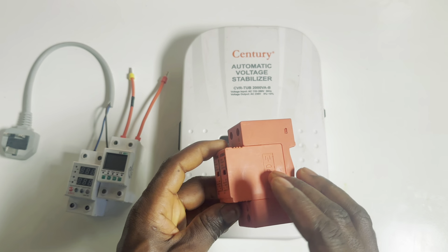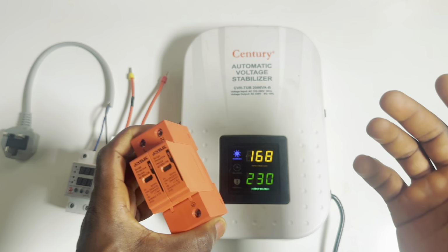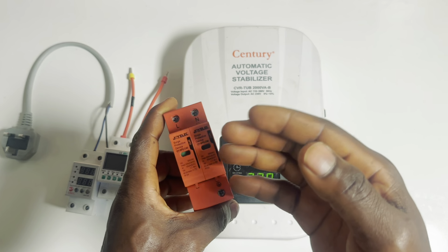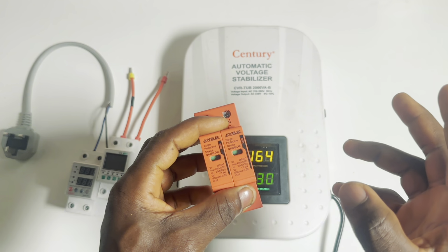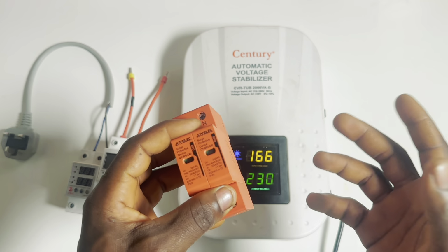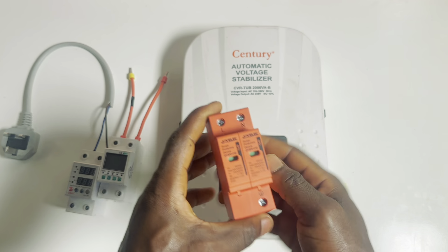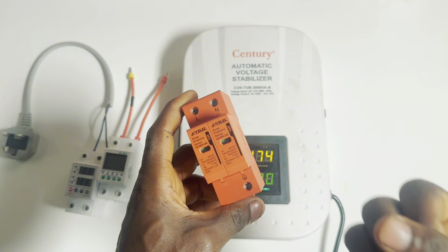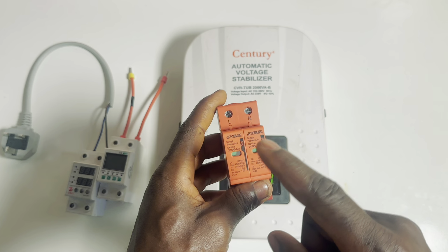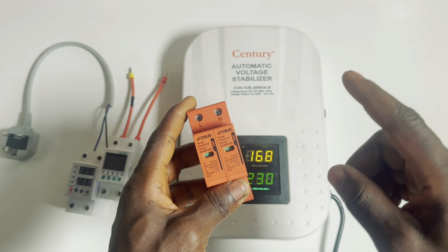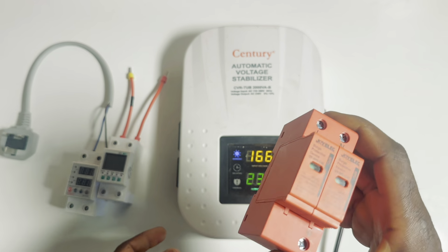So what this one does basically is protect your device from a thunder strike, and there are some kinds of surges that can occur from your inputs at some point. This can protect against them, depending on how it is. So that is basically the work of this one. It does not function alone. You need to ground it, and the basic function of this one is that, based on there already being an earth connection, it is going to divert that excess current that is coming. Instead of it passing through this and getting to your device, it is going to divert it into the ground. That is the functionality of this one.